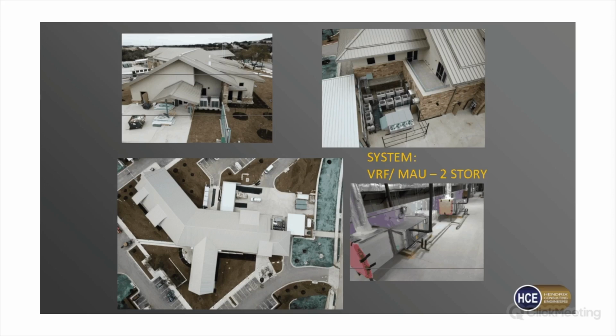This particular example is of an owner that wanted sloped metal roofs. It's a 2-story building, and this is a good application for VRF, mainly because it allowed us to not have any rooftop equipment, and allowed us to do all the heat rejection equipment on the edges of the building. You'll see there's an equipment yard on the far right, and a very small equipment yard on the far left - they're noted in the pictures at the top. The equipment yard on the far right is the upper right-hand corner picture, and the small equipment yard on the left is the upper left-hand corner.